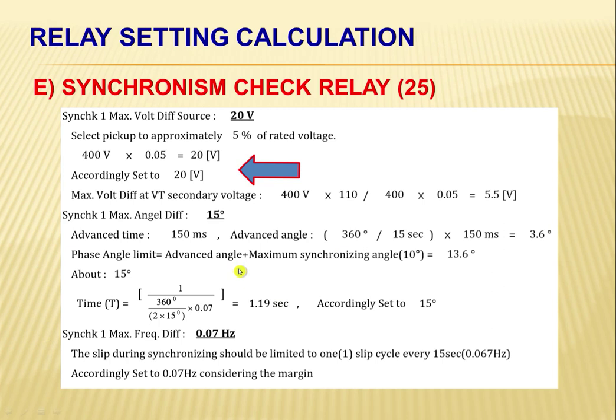Okay, to calculate the maximum angle limit, we need to add the advanced angle plus the maximum synchronizing angle, which is 10 degrees. To get this advanced angle, here we are nominating the advanced time. It is usual industry practice to have 150 milliseconds.